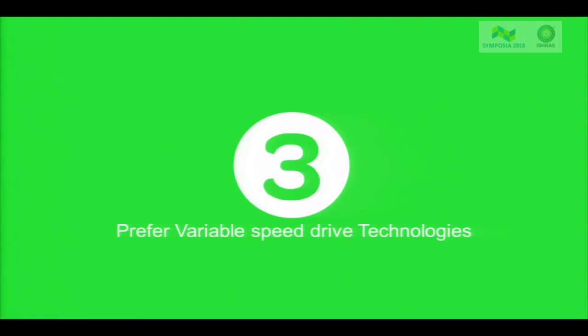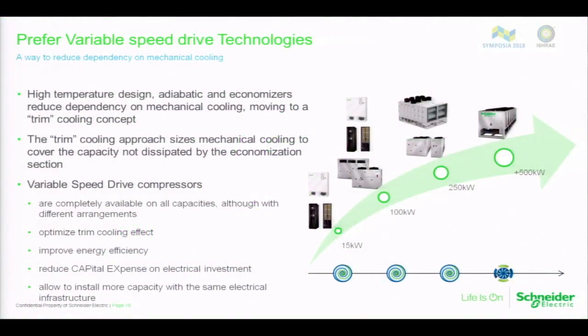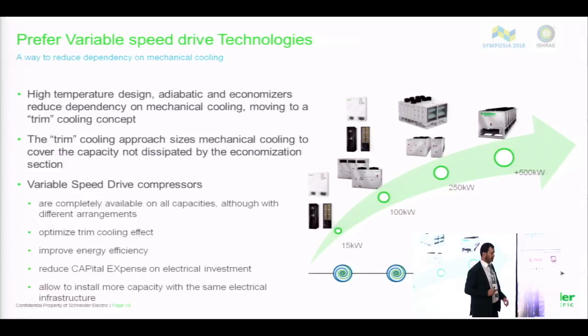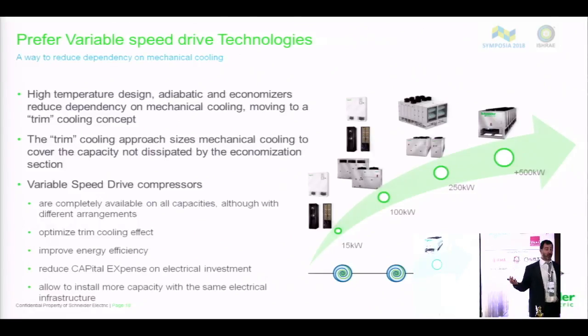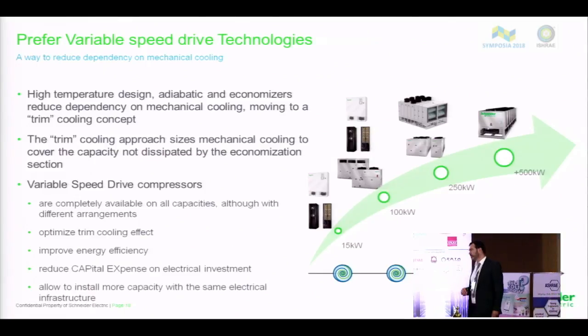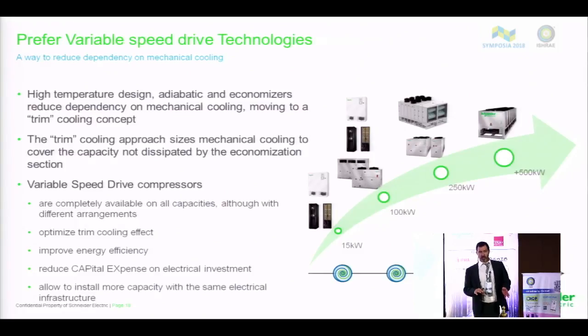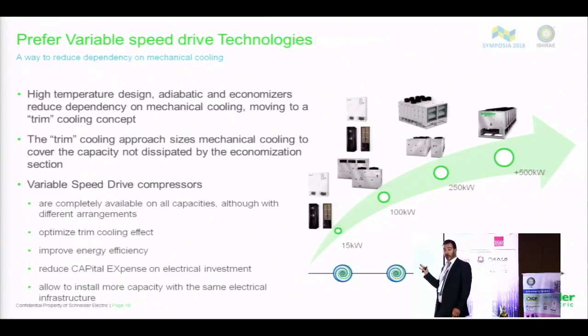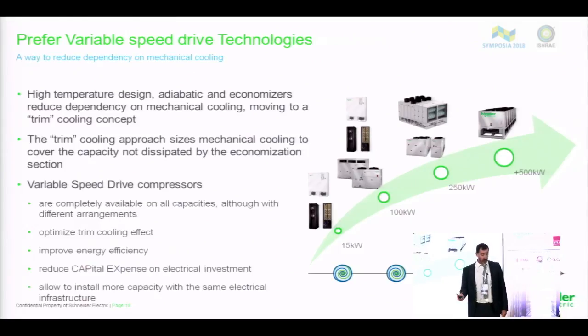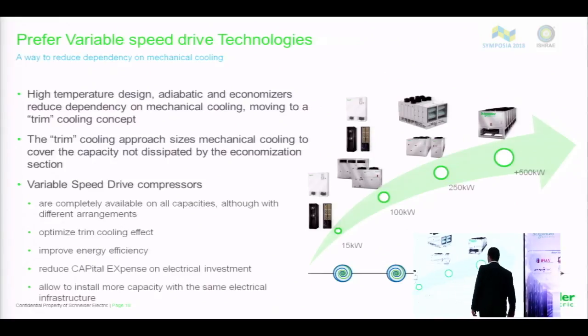Point number 3. Which kind of compressor and technology should I select? Now there are multiple compressor available, multiple fans, multiple motor, but one point is the more we use variable speed drive technologies on the pump, on the fan, on the compressor, the more we can improve the saving of the installation. It is something that need to be carefully analyzed with the ambient temperature as well, because even the inverter has some maximum ambient temperature operation, so it's not said that it's worldwide applicable. However, the more we use variable speed drive technologies, the more we are able to reduce the carbon footprint.